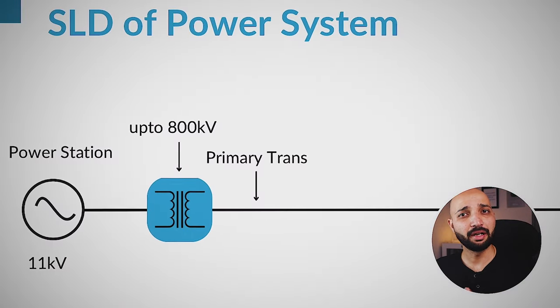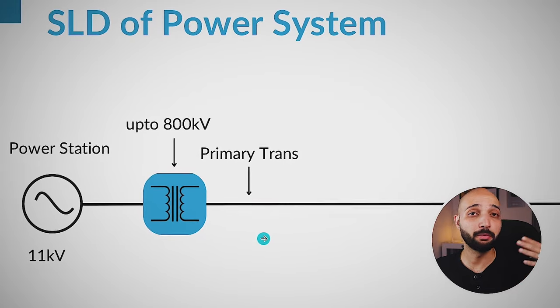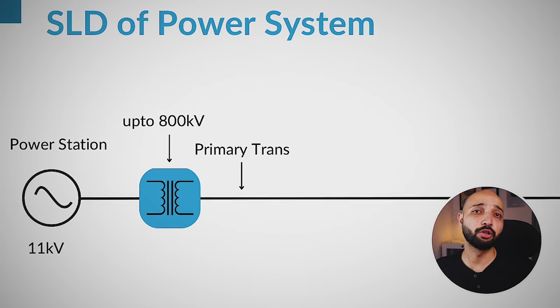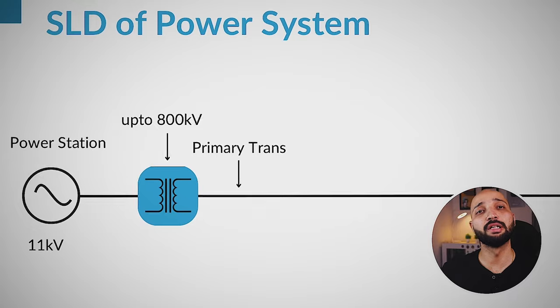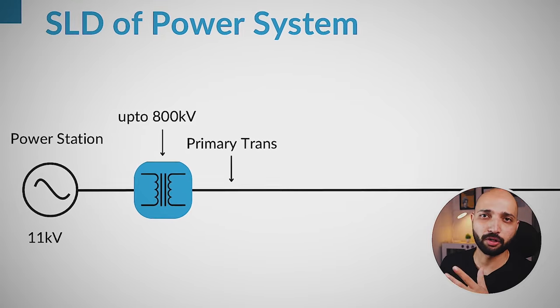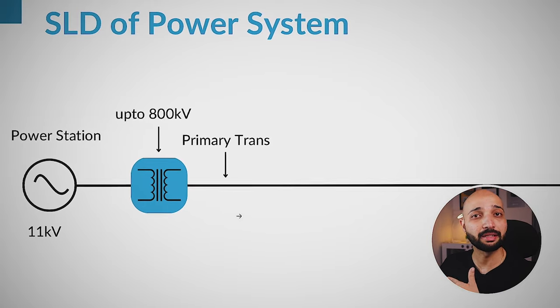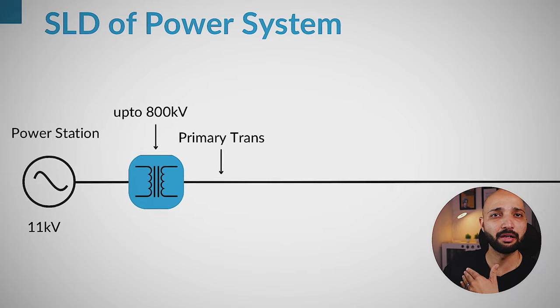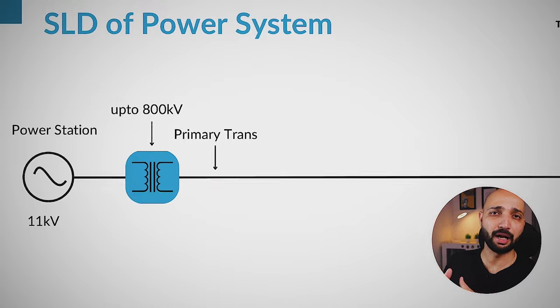The generating substation steps up the voltage to 145, 245, 400, or even 800kV. The voltage level depends on the distance the electricity needs to be transmitted — the higher the distance, the higher the voltage level. For example, if the distance is more than 200 kilometers, transmitting at 800kV or 420kV makes more sense than at 145kV. This transmission level is called primary transmission, covering voltage levels from 145 to 800kV.